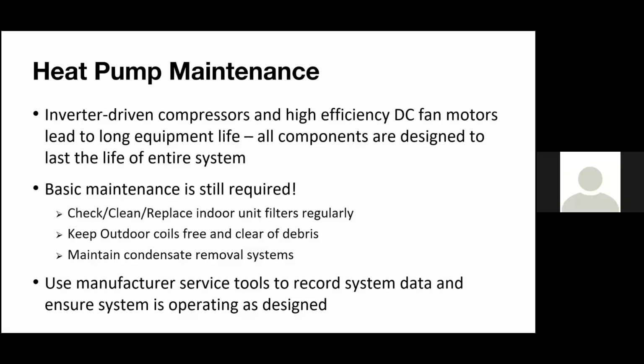So out of the box, a VRF system or a heat pump system basically needs little to no maintenance, right? We have inverter-driven compressors, we have high-efficiency DC fan motors, and all of these types of parts are designed to last the lifetime of the equipment. You don't need to schedule any maintenance calls, replace your blowers, your fan motors, compressors. None of that's needed. It should all be intact and survive 20, 25 years if need be, and potentially even longer than that. With that being said, don't ignore basic maintenance. That is still required, and it's very important, even though we're talking about filters here, right? One thing is you need to check, clean, and replace those filters.